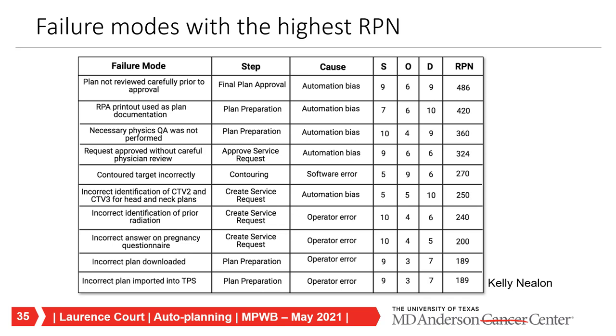Looking at the failure modes with the highest risk priority numbers (RPN), if you look at the cause column, there's not much caused by incorrect algorithms. Instead, there's a lot related to automation bias and operator error—things that can happen because of using AI tools but might not have happened otherwise. Automation bias is what happens when you get so used to the tool's results being good that you rely on them too much. Operator error is when something is entered incorrectly by the user—not the AI's fault, but it happens.